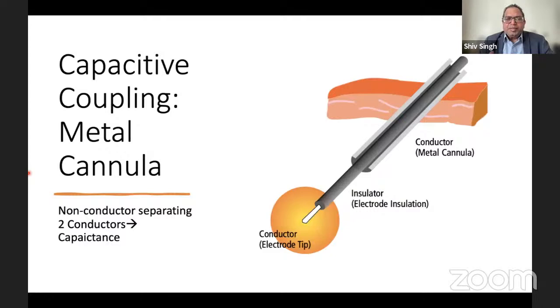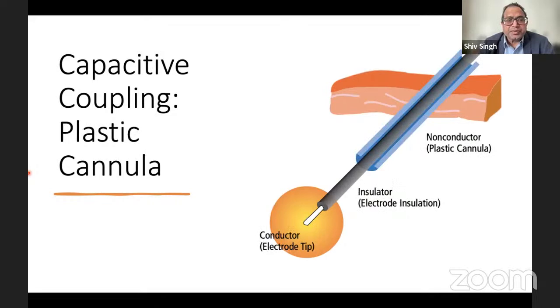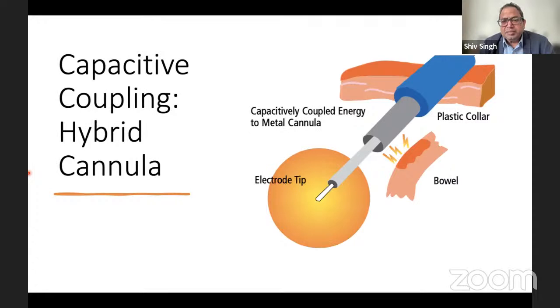Capacitors are formed when there are two metals separated by an insulator. Quite common: you have the metal conductor, you have an insulator inside, and then again a conductor with the tip. So the wire going through can cause capacitive coupling. This can induce heat within the metals commonly used in minimally invasive surgery, and if they're touching something else, that can cause problems. It's very common in these plastic cannulas, where there is metal, then plastic cannula, and then conductor again. And like I said, it's usually the bowel which comes in contact with this area, where there can be damage to the bowel.